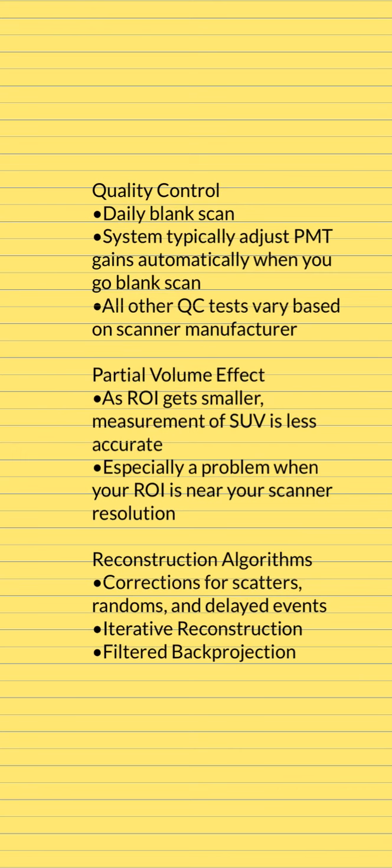And then all the other QC tests are really variable based on manufacturer. Most of the other tests just get really specific, and they're testing each part of your system. So they might test your ability to subtract randoms and scatters out of your overall image. It'll test your light output for your crystals.